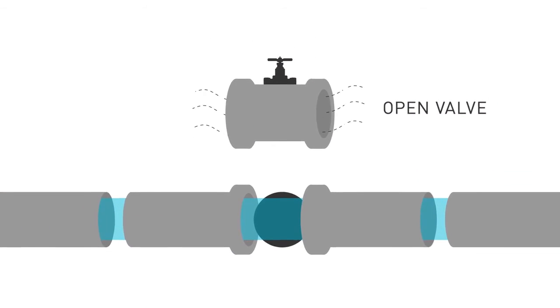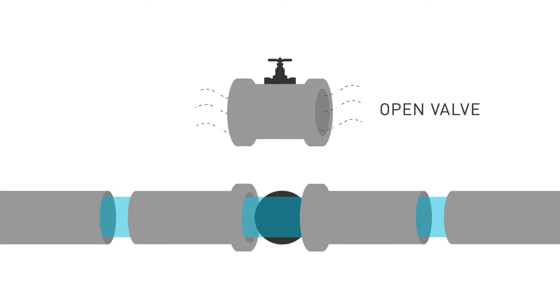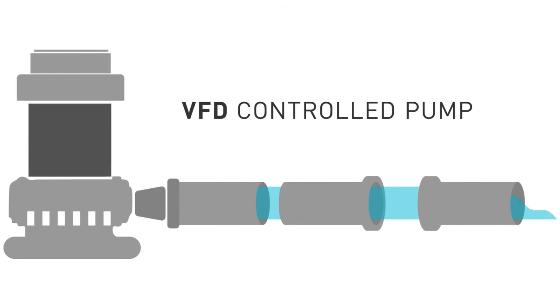If you have an application where you have vanes and dampers or maybe you have a control valve that's controlling the flow of a material, you can actually remove the vanes and dampers. You can remove the control valves and now use the speed of that fan or the speed of that pump to control the flow of that material. And you can save an incredible amount of energy just by doing this.